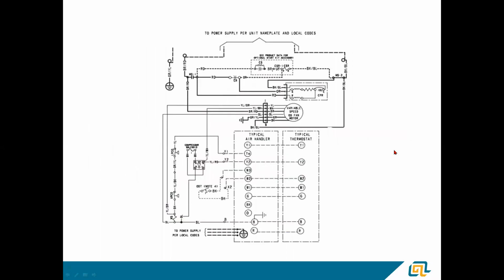And a quick little wiring diagram for one of them. This is actually a single compressor, 2-speed. It's got the variable speed outdoor fan motor on it. And you'll notice the larger wires coming in, of course, that's our high voltage. We've got a black and a blue and a brown and a red delivering high voltage to the motor. Green and yellow is our ground. Okay. And then we got the 24 volt signal coming into the fan motor.